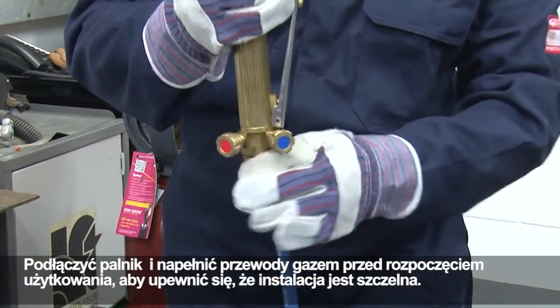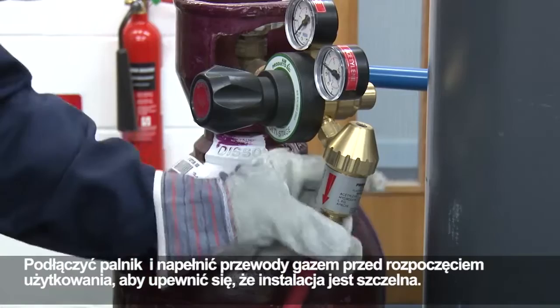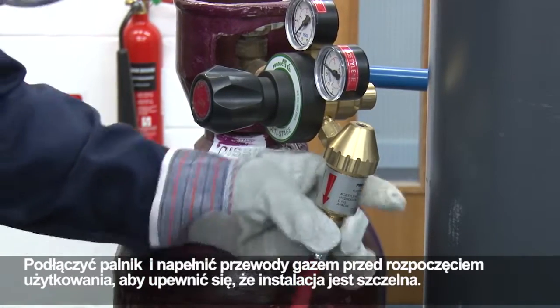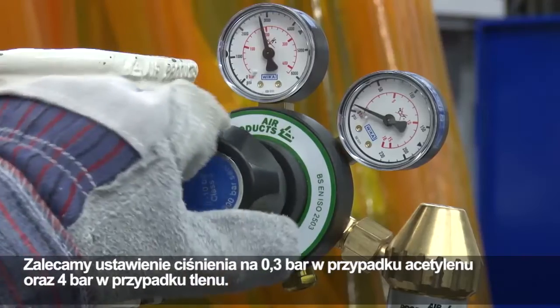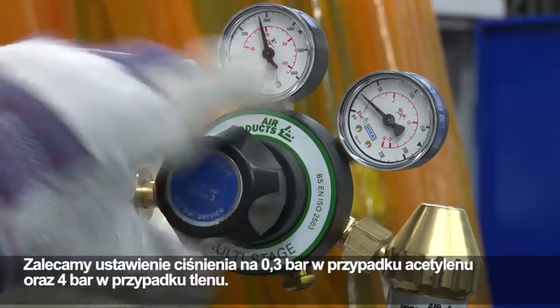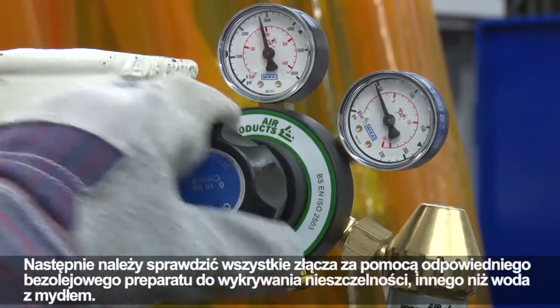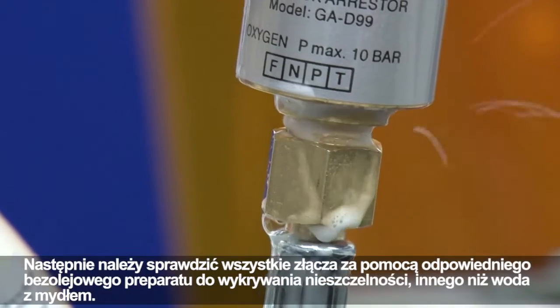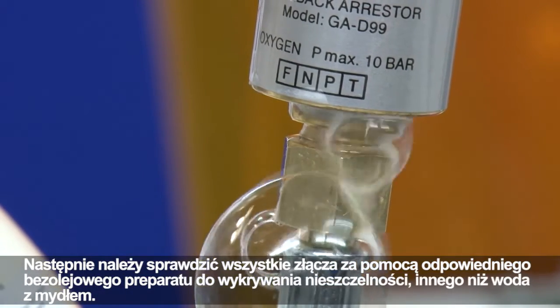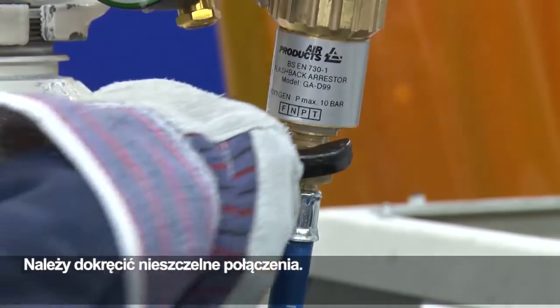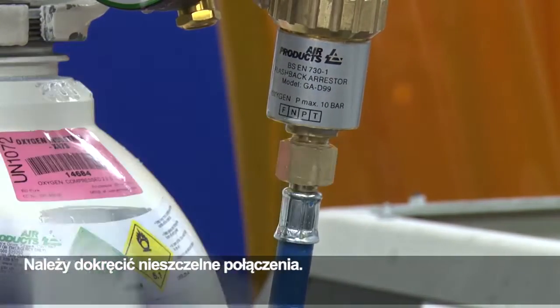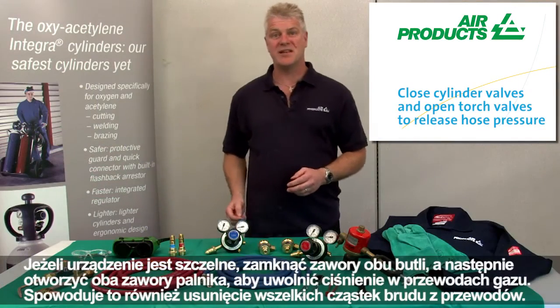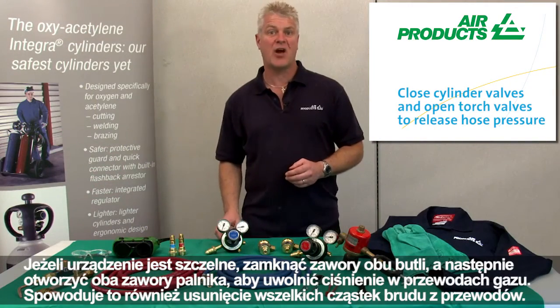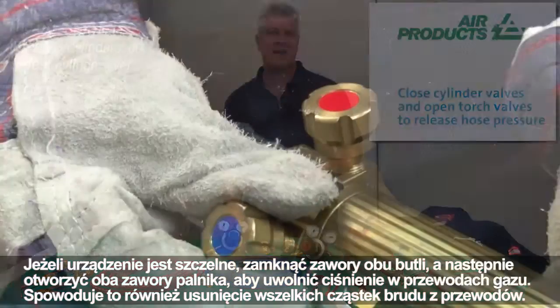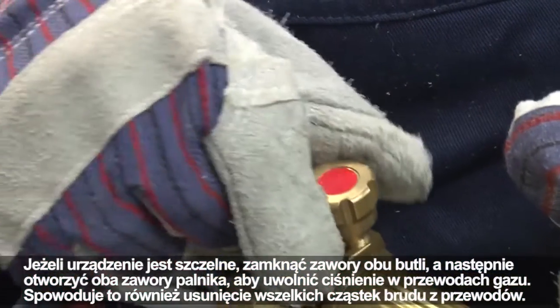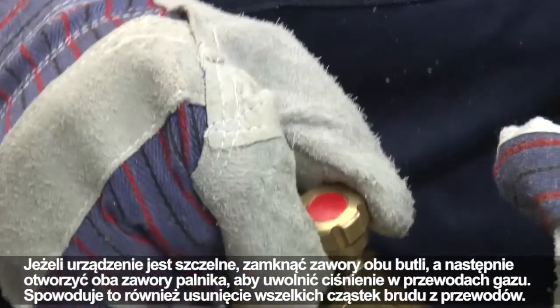Connect the cutting torch and pressurise the system before use to ensure the system is leak-free. We recommend setting the pressures to 0.3 bar for acetylene and 4 bar for oxygen. All joints should be checked using a suitable oil-free leak detection solution, not soapy water. Any leaking joints caused by loose fittings should be tightened. If the equipment is leak-tight, close both cylinder valves and then open both torch valves to release pressure in the gas hoses. This also will remove any particles present in the hoses.